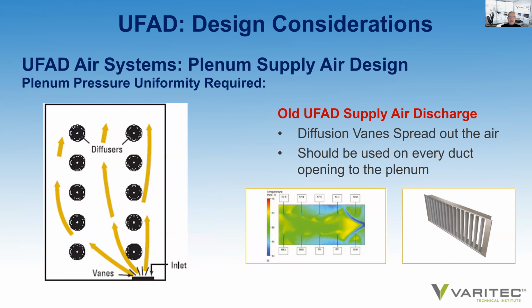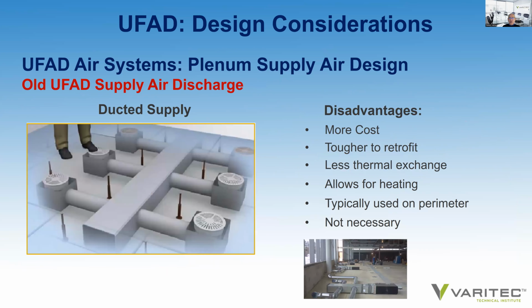In the old days, you used turning vanes at the injection point to allow for a wider distribution of supply air out of the register to promote uniformity of pressure under the floor. That's how it was done in the older days. Another solution in the old days was to have ducted floor diffusers.